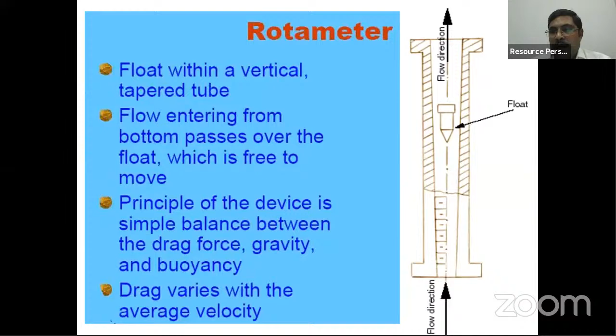This should be 2 for better accuracy, the ratio of the density of the float and the flowing liquid. If it is more than 2, then you will end up losing accuracy. Again, the rotameter is designed for one particular density, as I already mentioned. The rotameter can take care of density variation of maybe a maximum of about 2 to 5%, not more than that. If the density variation is more than 5%, then the rotameter cannot give the reading. So the rotameter is ideally suited for liquid flow measurements. There are versions available for air, but if you use it for air measurement, then you will not get an accurate reading.